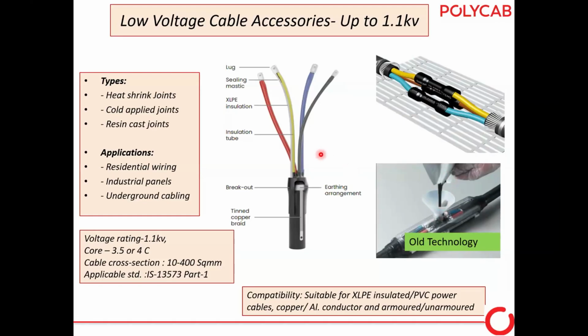But in the heat shrink joints, you can prepare the cable, do the ferruling activity, shrink the tubes, and immediately you can charge. So within half an hour, you can do the heat shrink jointing work and charge the system. That's the best part of the heat shrink cable accessories in the low voltage. Instead of using the resin cast joint, you can use these heat shrink technology joints and terminations and save the time and save the environment. This comes in 3.5 core, 4 core, single core, 2 core, depending on your cables. Its cross section is 10 to 400 square mm, even 630, 800 is possible. We have done type testing as per IS 13573 part 1.